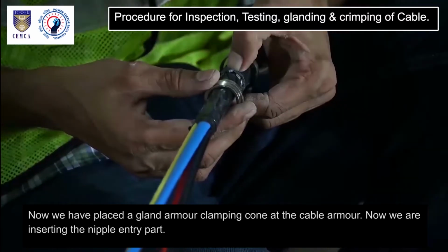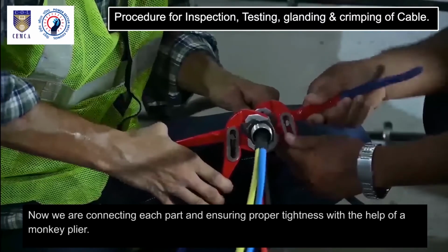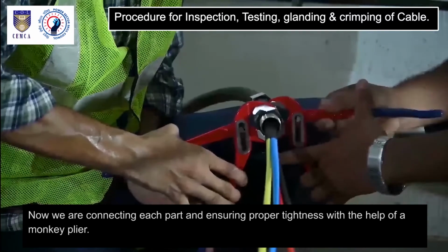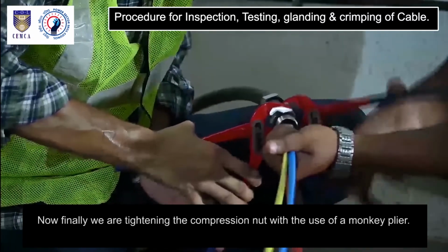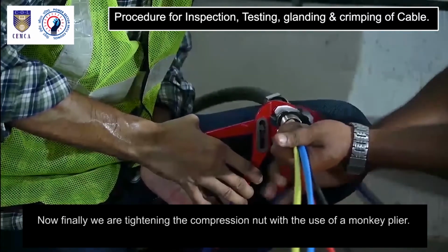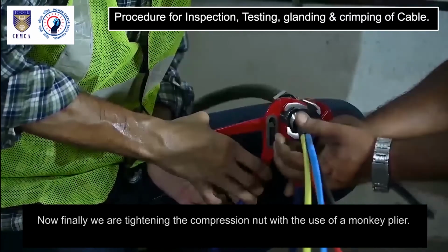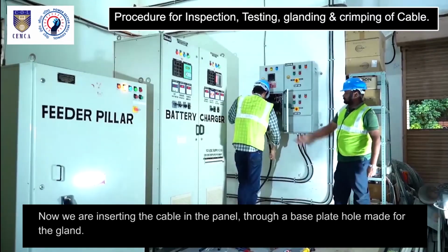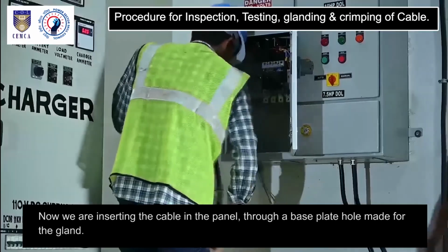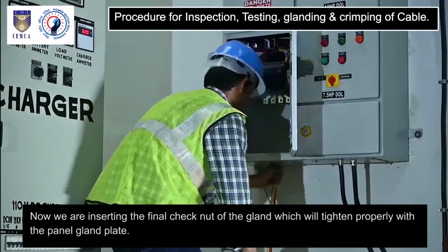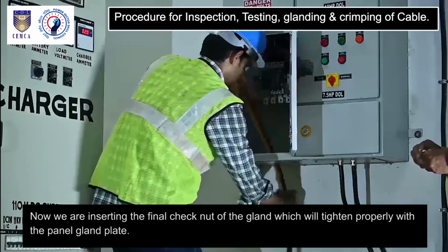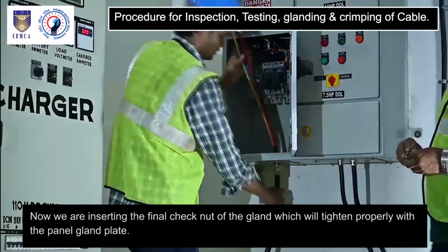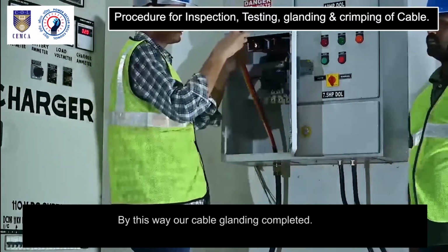Now we are inserting the nipple entry part. Now we are connecting each part and ensuring proper tightness with the help of a monkey plier. Now finally we are tightening the compression nut with the use of a monkey plier. Now we are inserting the cable in the panel through a base plate hole made for the gland. Now we are inserting the final check nut of the gland which will tighten properly with the panel gland plate. By this way, cable glanding is completed.